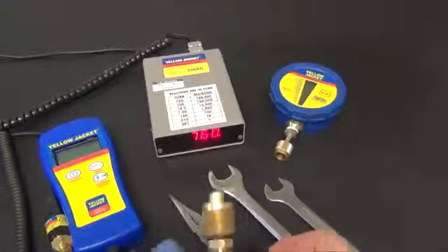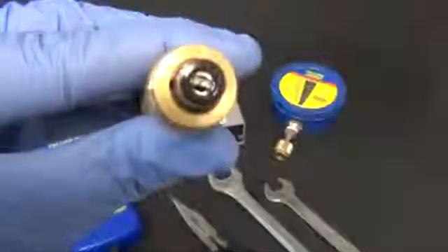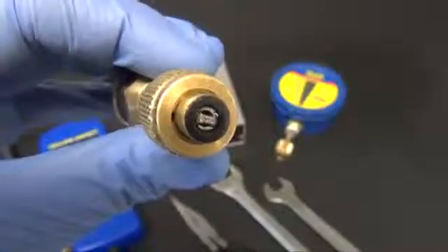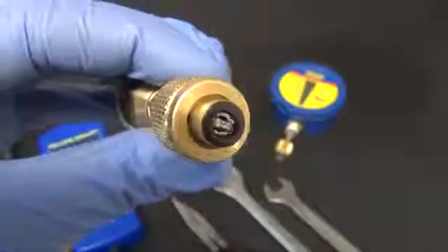We can first do a visual inspection of the gasket and the depressor. First look at the gasket for any obvious signs of oil. The gasket will appear wet or shiny. If so, there is oil contamination.